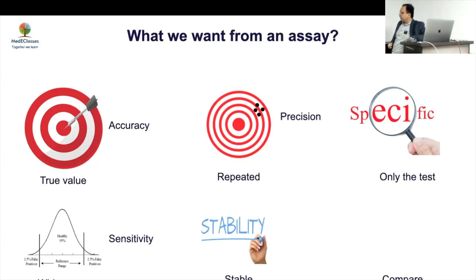And second, as I hinted earlier, it should be stable. So if I keep it here for maybe a week or 2 weeks or whatever, it should not be affected. So that's the assay stability. And finally, you are comparing it with an ideal situation and you want a reference where standards have been maintained. So for a lab to have a good result, you want a true value which is repeatable, which is specific to that particular test, which gives you good sensitivity and stability, and is always validated with different reference standards, which becomes important from that perspective.